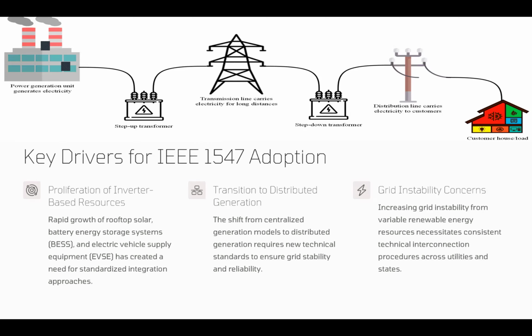Now, IEEE 1547 defines some interconnection rules, trip or reconnection criteria, and anti-islanding protection, so we can make sure that those DER behave predictably. By mandating the parallel operation guidelines, we make sure that those DER are synchronized with the grid, for both voltage and frequency, before they are integrated or reconnected to the grid.